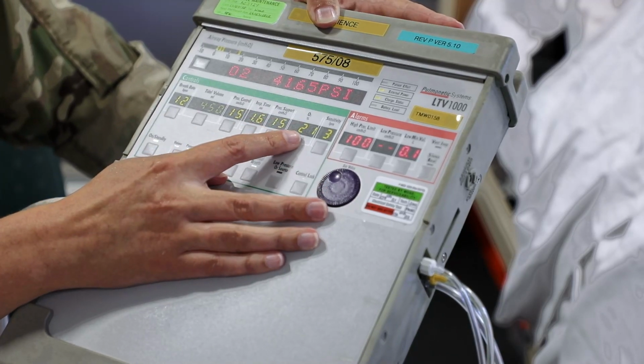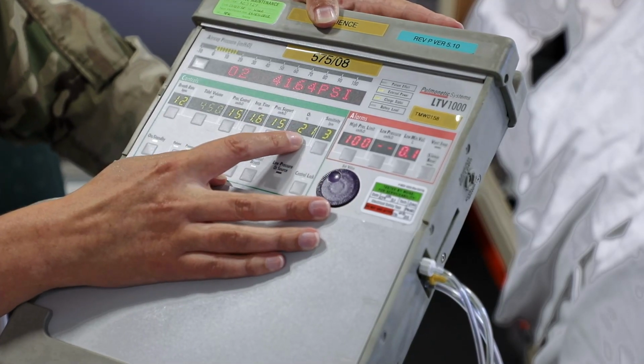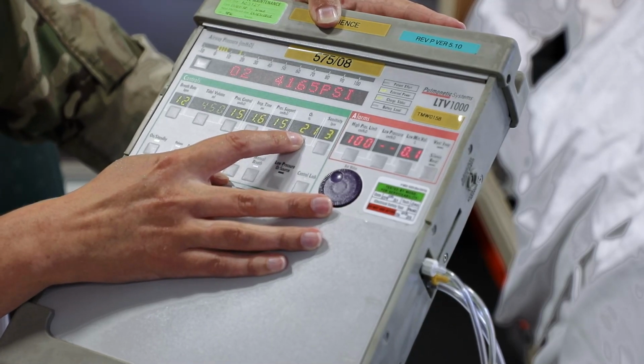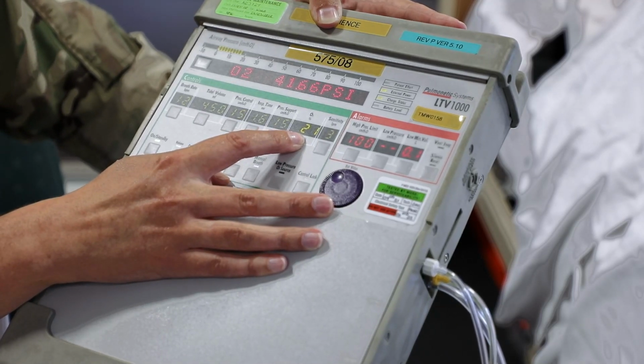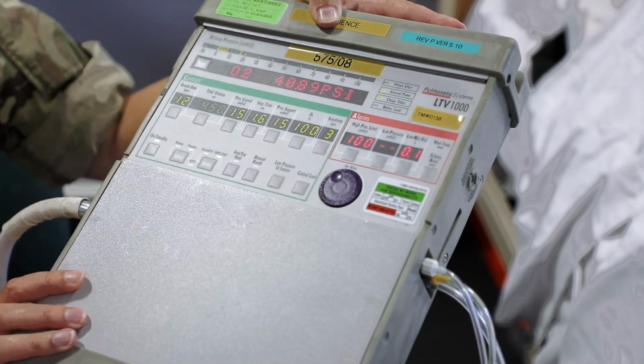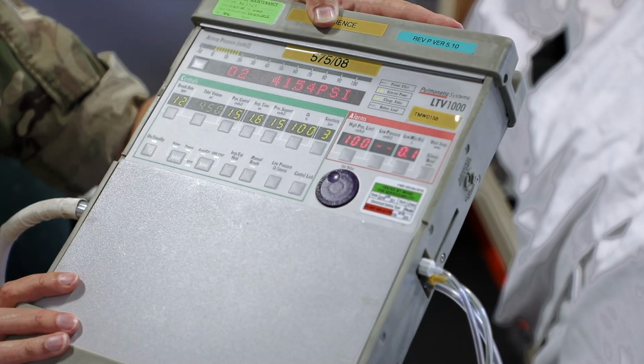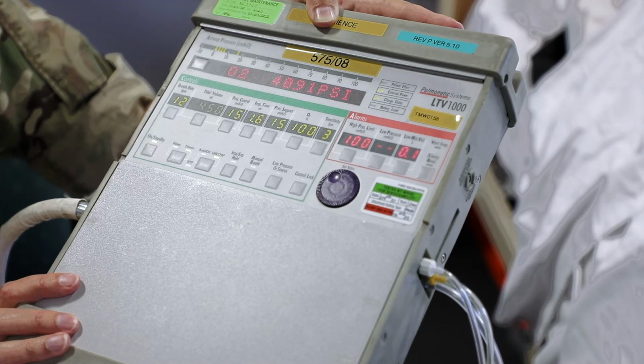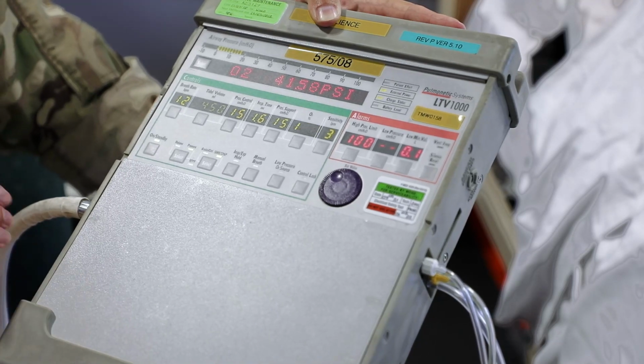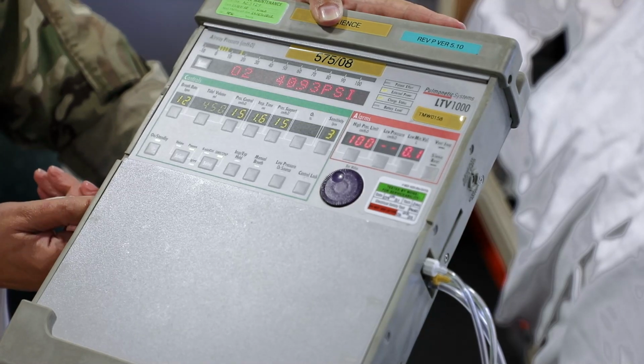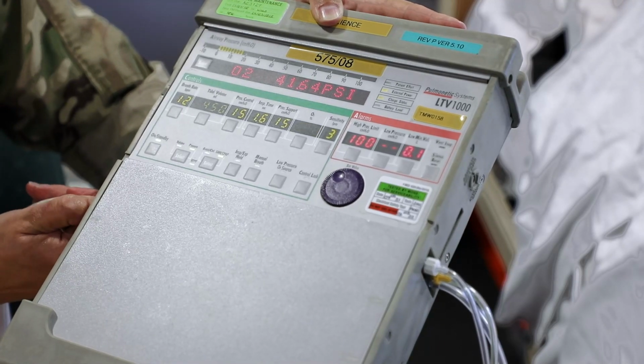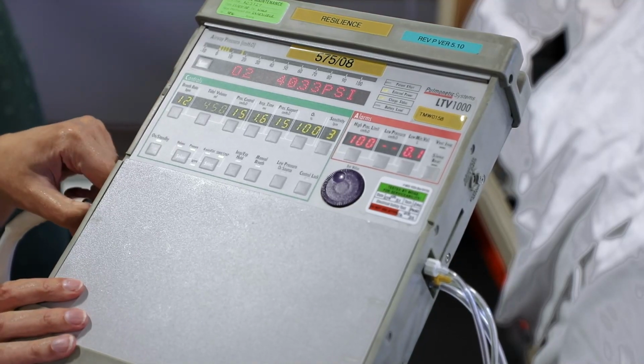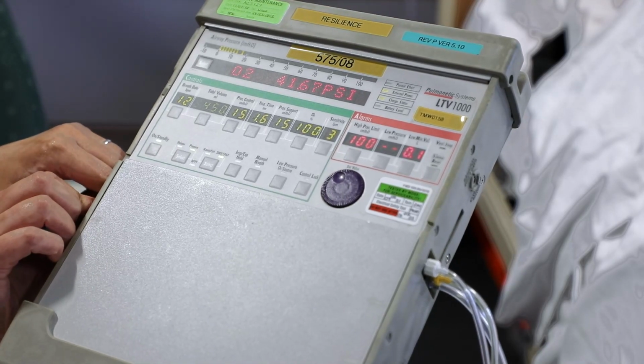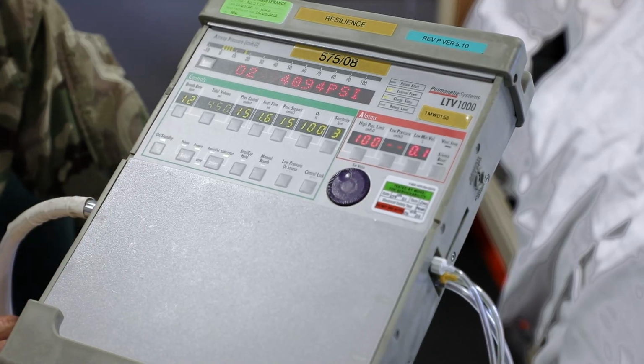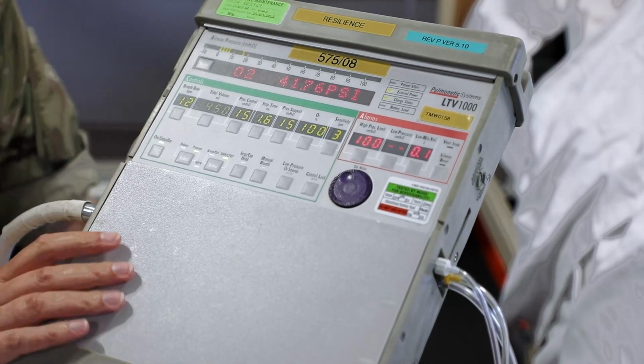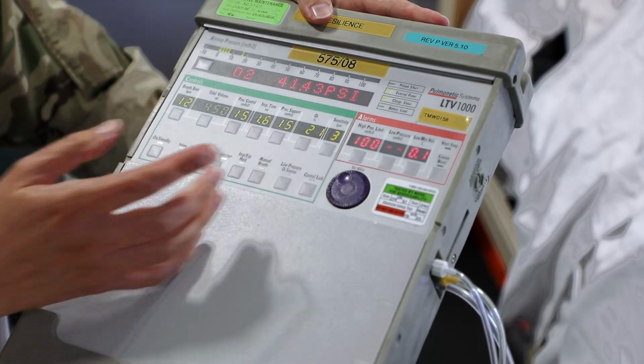So I'll show you what happens with a poorly functioning oxygen hose. If I deliver 100%, you can see how that PSI drops off. So this oxygen hosing isn't functioning the best it can be. To troubleshoot, make sure you tighten up any connections. Actually, a bit of tightening up there has improved the PSI already. And have a good look at your oxygen cylinder to make sure that you've got some oxygen connected. So we'll pop that back down.